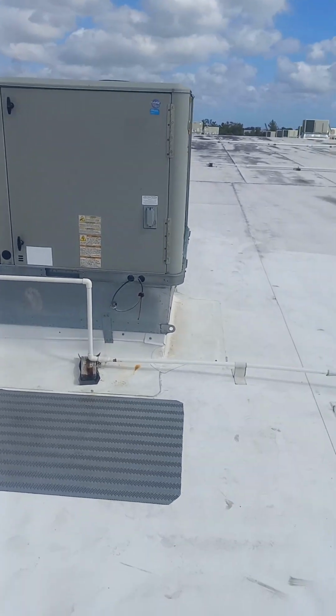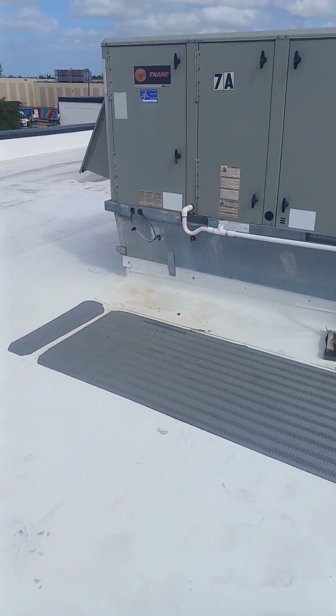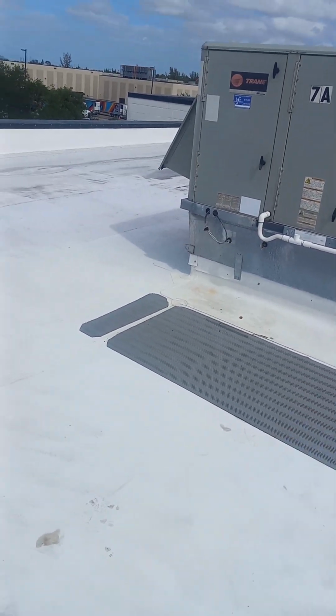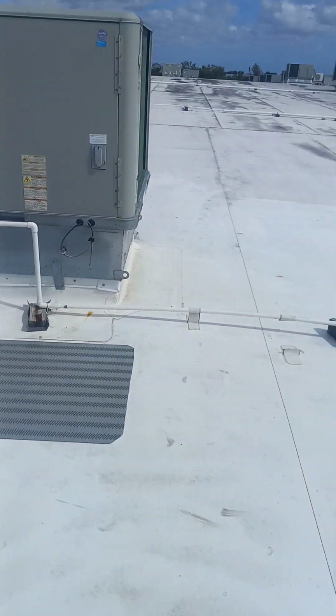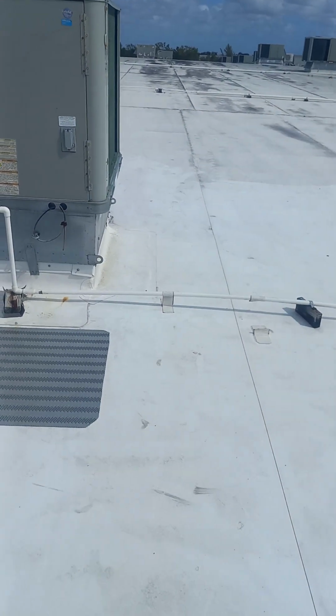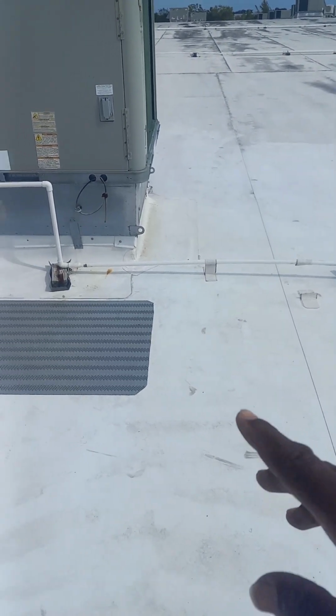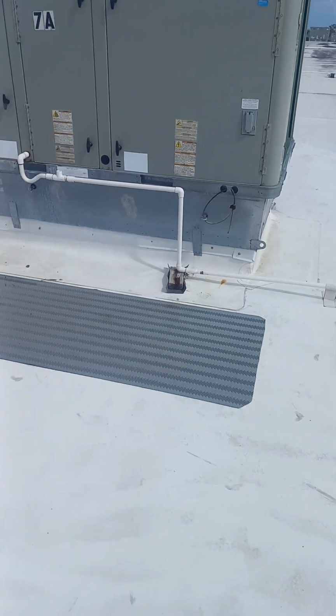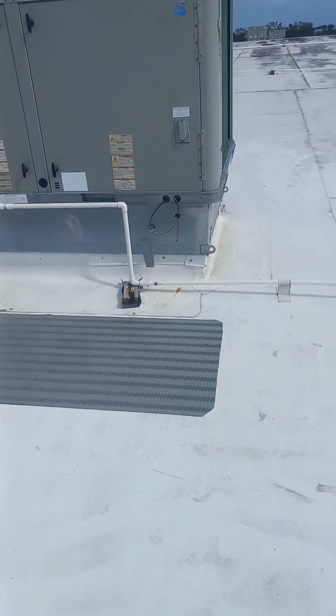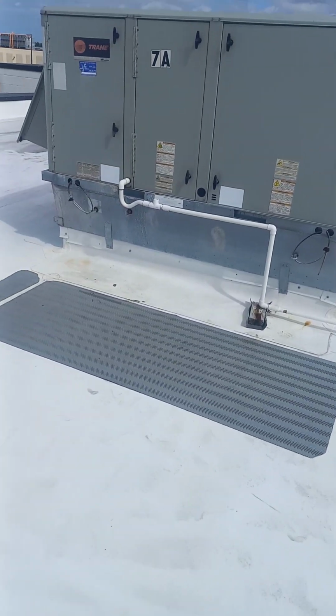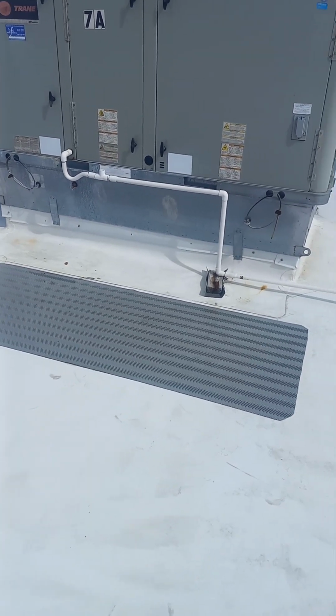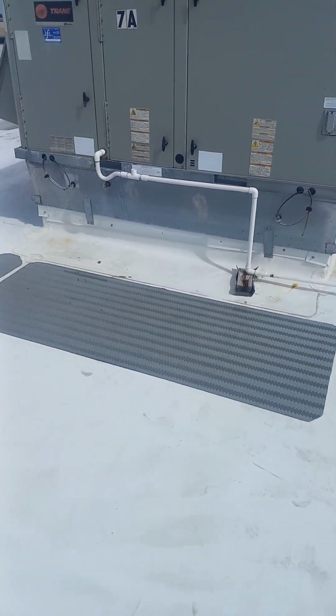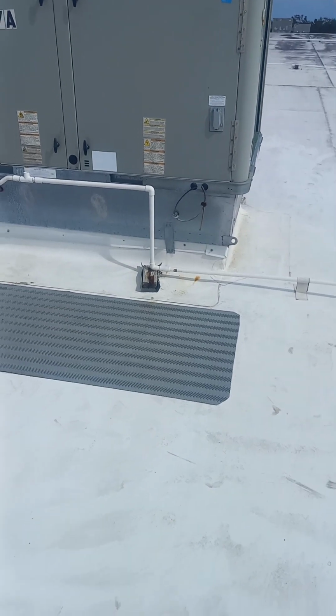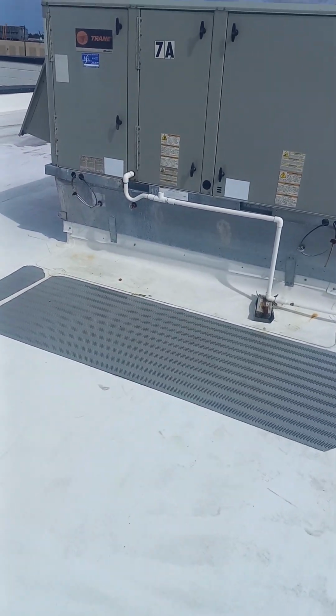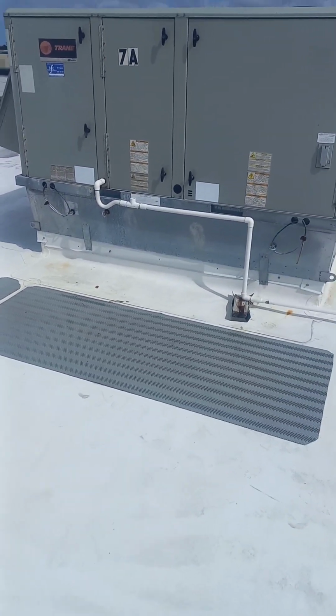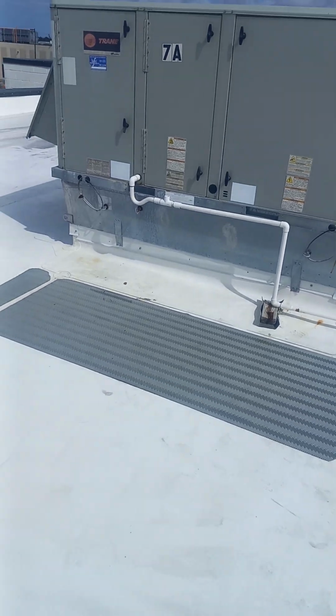It's Trane again. So this unit, first of all, this building is a cinder block building with metal framing and the roof section. They have foam, and then after the foam, they put a membrane over it to prevent the water from going on the inside. But these units, what they did, when they do construction and everything, each one of these, they follow the plans, they cut the holes out in the metal roofing, and then they create a curb.